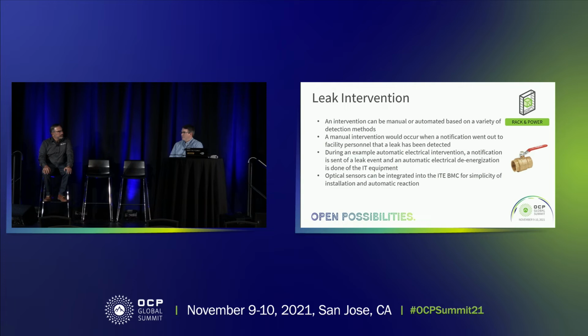For this audience at OCP, it's really key to say it is about uptime, but also about balancing scale. So it's one thing to detect a leak along a facility pipe—is that necessarily a problem requiring immediate shutdown of the IT? Maybe, maybe not. But detecting a leak at the facility level versus on a cold plate loop within a server are two different things that probably need different response times. So we do talk about that.